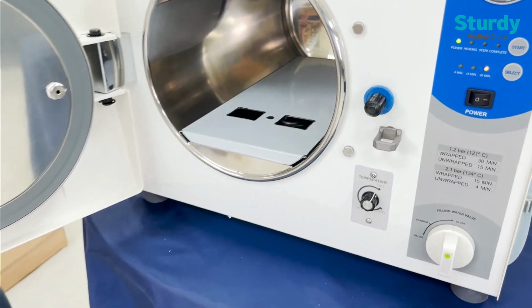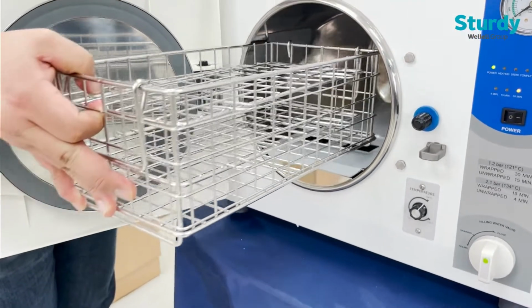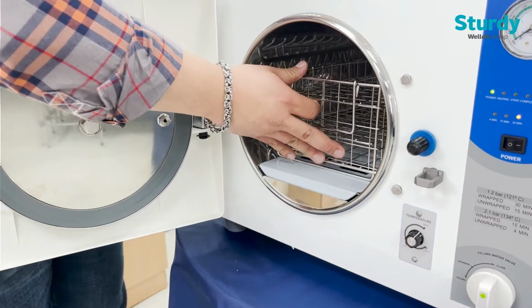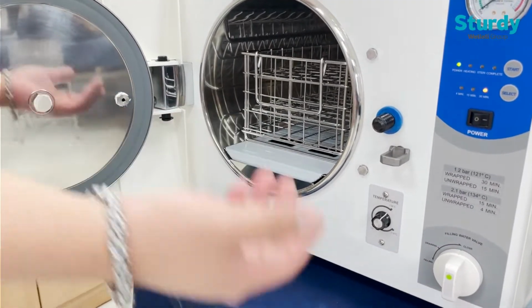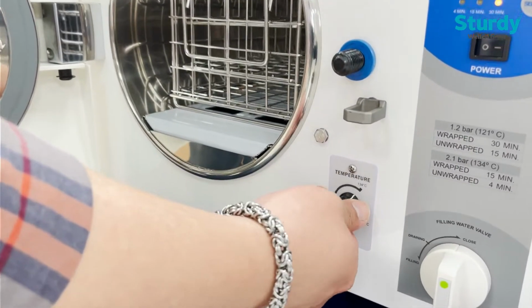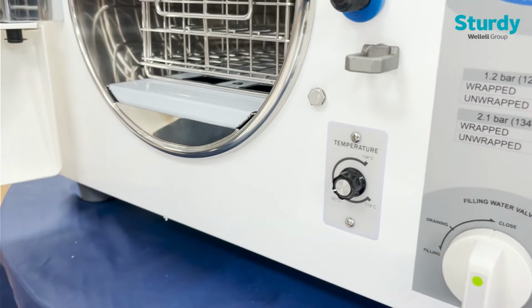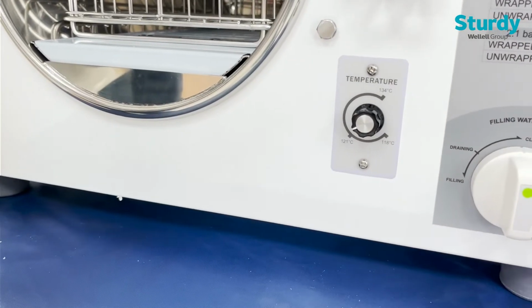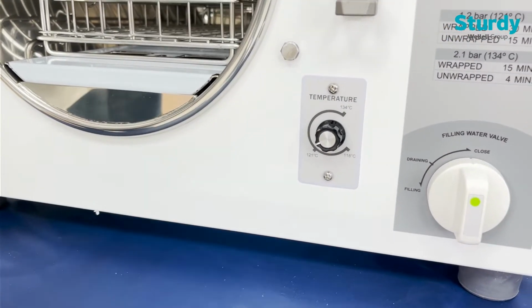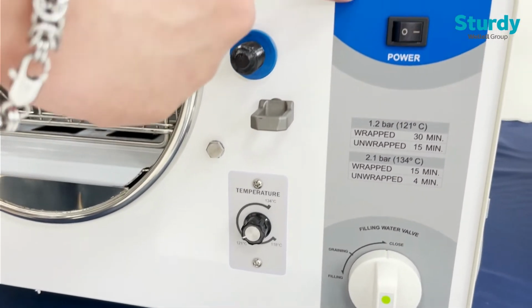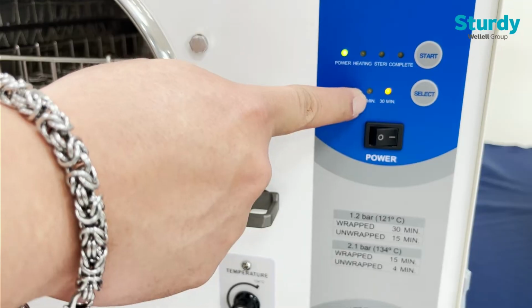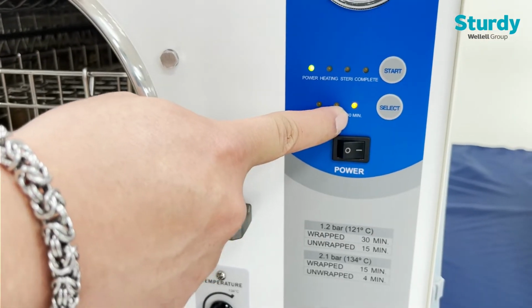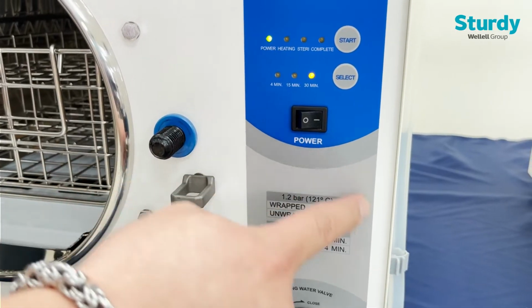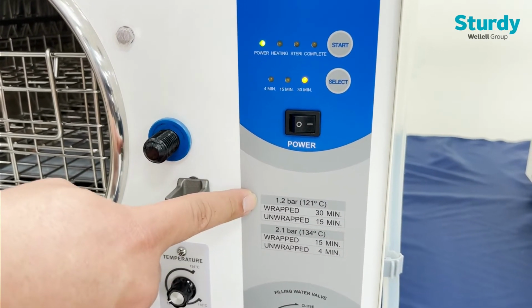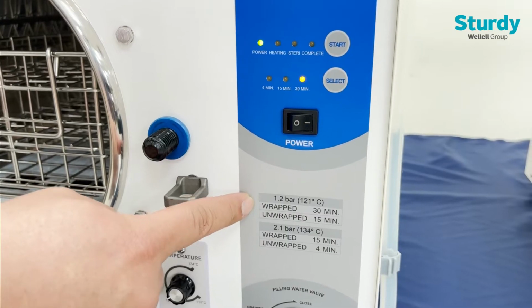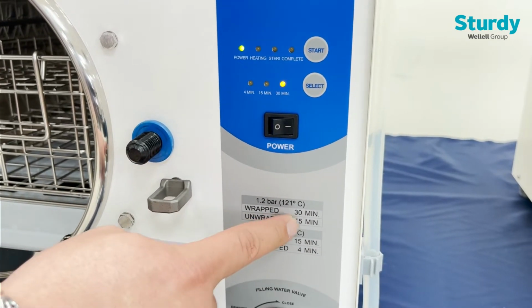Next, we will input the objects that will be sterilized. Next, we will adjust the temperature either to 134 degrees Celsius or 121 degrees Celsius, depending on the object that you want to sterilize. Next, we'll select the sterilization time from 4 minutes, 15 minutes, or 30 minutes max. There's a recommendation label that appears on the control panel indicating the temperature and time of sterilization for the object, whether it is wrapped or unwrapped, and individually.